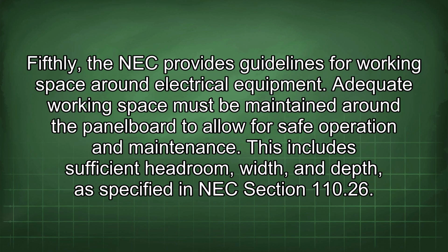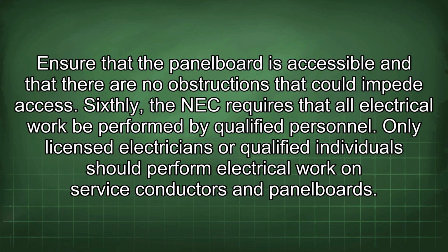Fifthly, the NEC provides guidelines for working space around electrical equipment. Adequate working space must be maintained around the panel board to allow for safe operation and maintenance. This includes sufficient headroom, width, and depth, as specified in NEC Section 110.26. Ensure that the panel board is accessible and that there are no obstructions that could impede access.